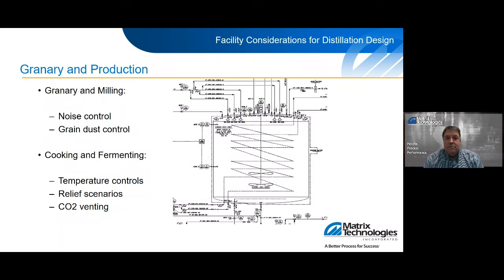Like I said, quick overview of the process. Our spirits are made from the natural grains of corn and rye and malted rye, and they're typically delivered in bulk and stored in bulk, and they need to be ground and milled. That milling, the grain handling and milling steps, are very noisy, and there's a grain dust explosion concern as well. So those things need to be designed into the spacing and the venting of those rooms.